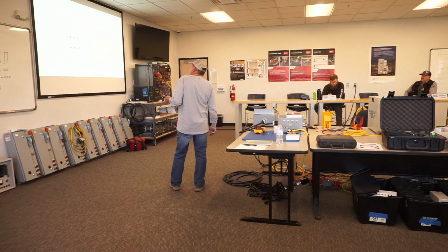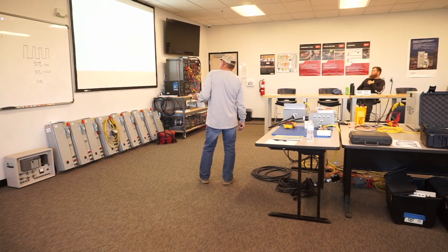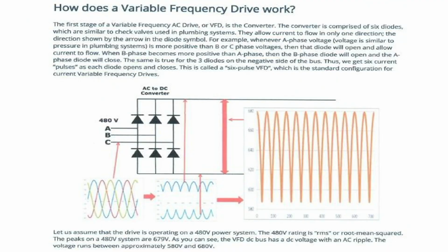So basically, how does it work? First stage is the converter section. There's what we call a 6-pulse drive, because each one of these diodes puts out a pulse. So A phase, I've got a positive pulse, and I'm taking this negative sine wave and turning it into a positive pulse. And then B phase comes along, 120 degrees later, starts doing the same thing. So my DC bus sees this coming in. And then along comes the capacitor, and the capacitor fills in these hollow spots to smooth this out to where it looks like a flat line. Any questions? Understandable?